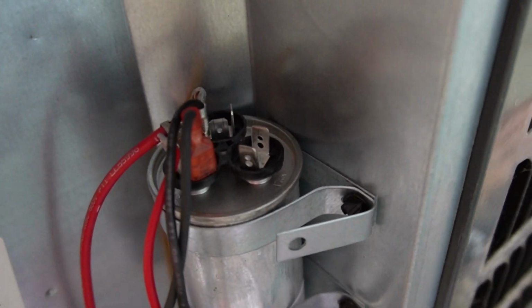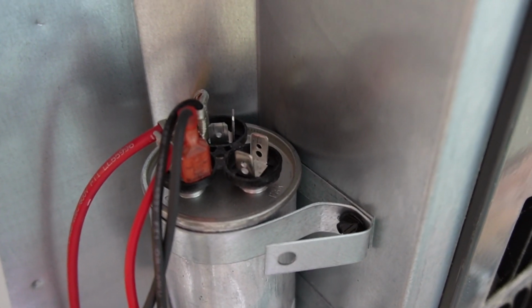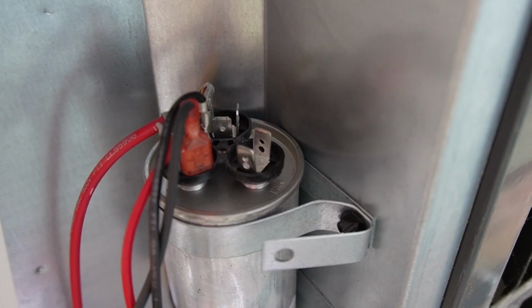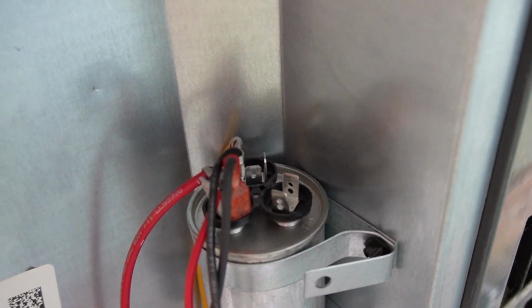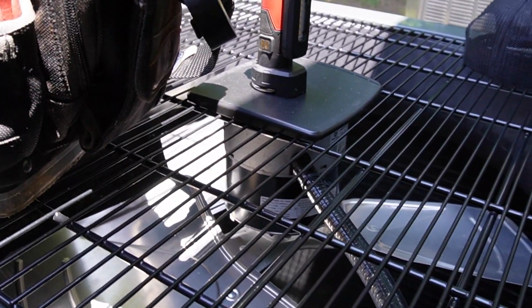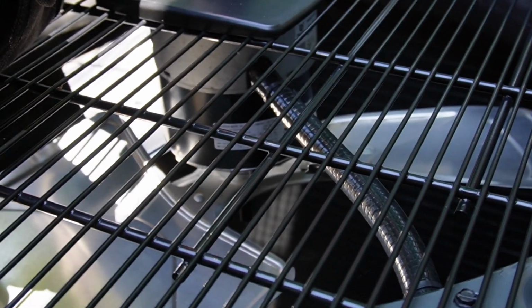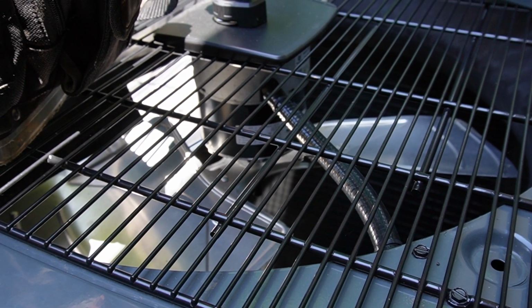And on these type of systems, they do have a dual capacitor here, but you see nothing's hooked up to the fan side, so they could have gone with a single. The reason for that is your fan motor is electronically controlled. So we'll get this thing fired back up here and let you see it in action.